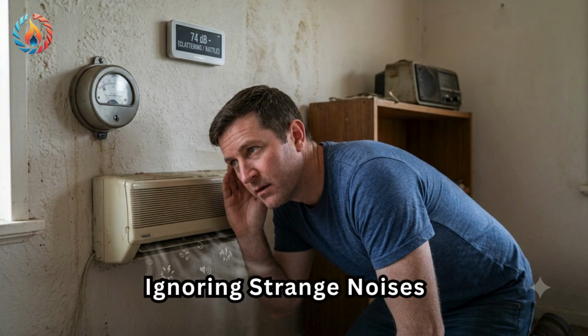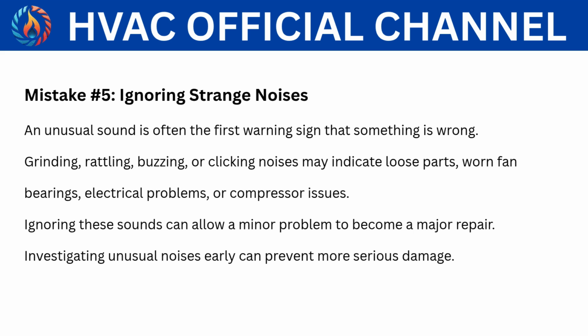Mistake number 5. Ignoring strange noises. An unusual sound is often the first warning sign that something is wrong. Grinding, rattling, buzzing, or clicking noises may indicate loose parts, worn fan bearings, electrical problems, or compressor issues. Ignoring these sounds can allow a minor problem to become a major repair. Investigating unusual noises early can prevent more serious damage.